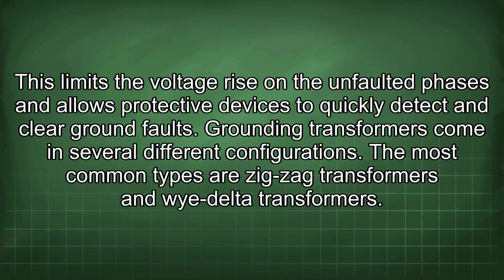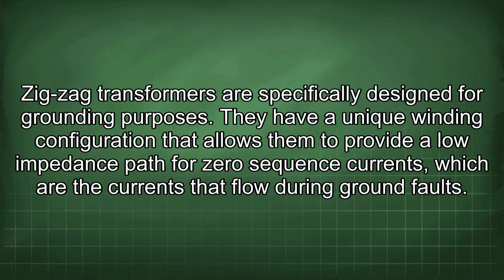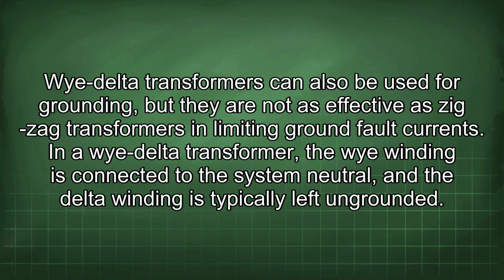Grounding transformers come in several different configurations. The most common types are zigzag transformers and Y-delta transformers. Zigzag transformers are specifically designed for grounding purposes. They have a unique winding configuration that allows them to provide a low impedance path for zero-sequence currents, which are the currents that flow during ground faults. Y-delta transformers can also be used for grounding, but they are not as effective as zigzag transformers in limiting ground fault currents. In a Y-delta transformer, the Y winding is connected to the system neutral, and the delta winding is typically left ungrounded.